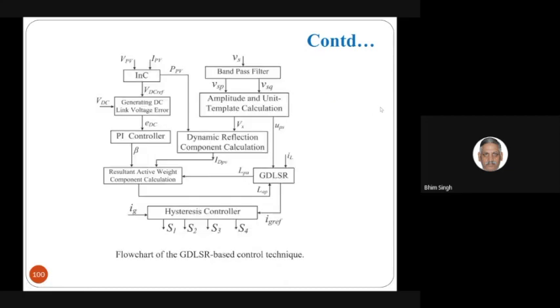And this is the typical control scheme. For the reference DC link voltage, you get it from the MPPT algorithm, and then we use the controller as shown in the block diagram. This is typically for voltage regulation, and the reactive component current. So one is the active component, another is the reactive, and from that we get the reference current, and we control the grid current and maintain it in phase with the supply voltage, sinusoidal current, irrespective of the voltage being distorted.